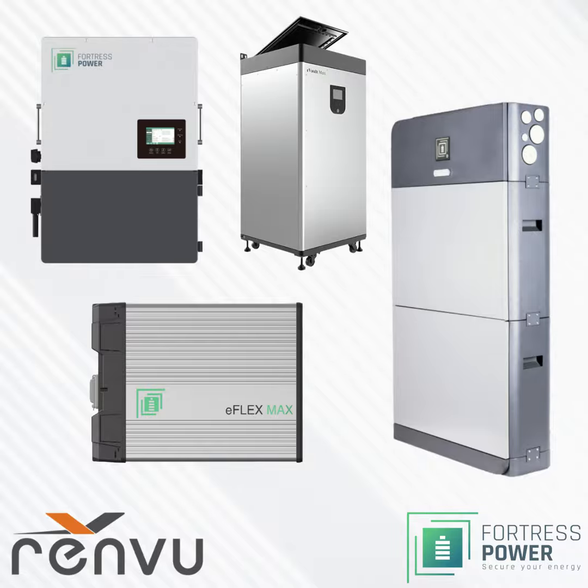Real quick, touch on the Durac. So the Durac, anybody that's installed our old eFlex that wasn't outdoor rated knows the Durac. You can put up to 4 eFlex Maxes or eFlexes into this. With the eFlex Max, it's not required anymore because the eFlex Max is fully outdoor rated. But if it's a space issue and you want to put 4 eFlex Maxes into this, you can absolutely do it. Makes it very clean, easy to install. They all hook up to one, and then you connect the inverter directly to the terminal on the Durac.